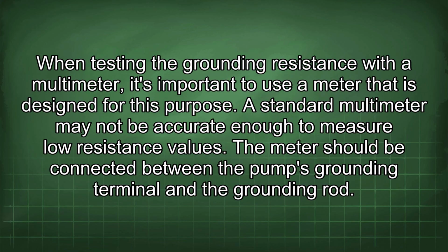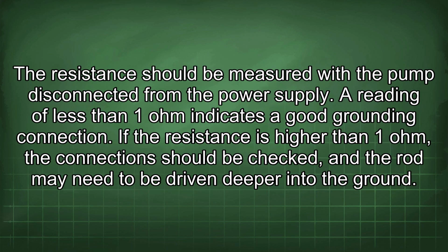When testing the grounding resistance with a multimeter, it's important to use a meter that is designed for this purpose. A standard multimeter may not be accurate enough to measure low resistance values. The meter should be connected between the pump's grounding terminal and the grounding rod. The resistance should be measured with the pump disconnected from the power supply. A reading of less than 1 ohm indicates a good grounding connection. If the resistance is higher than 1 ohm, the connection should be checked and the rod may need to be driven deeper into the ground.